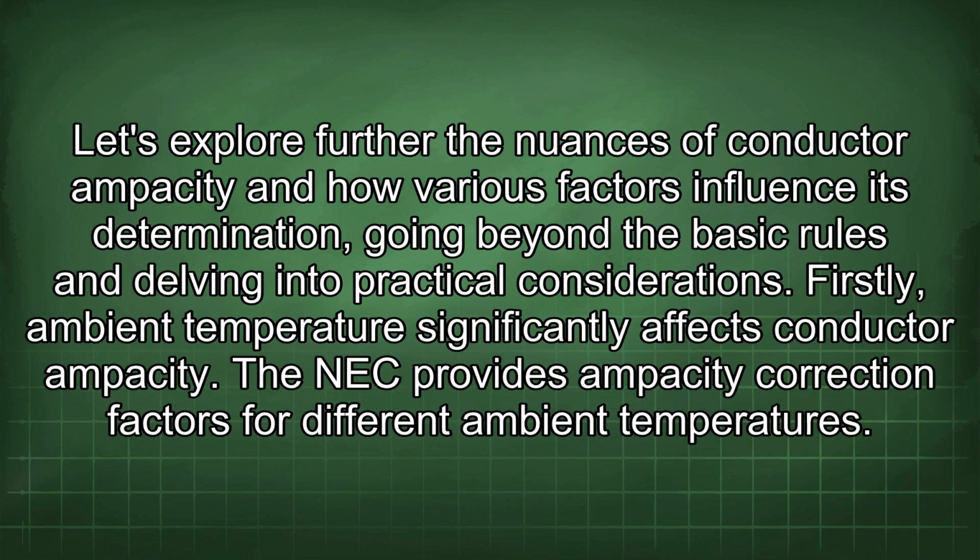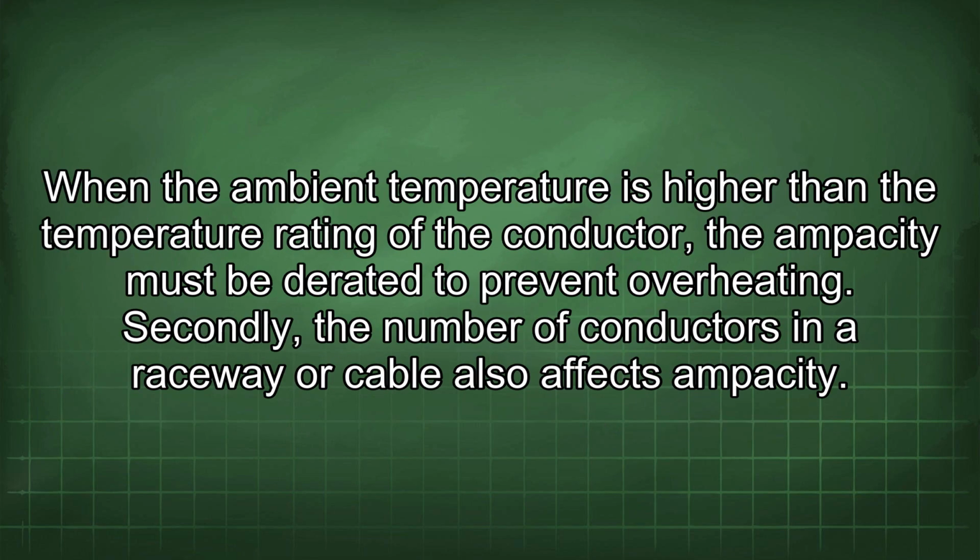Let's explore further the nuances of conductor ampacity and how various factors influence its determination, going beyond the basic rules and delving into practical considerations. Firstly, ambient temperature significantly affects conductor ampacity. The NEC provides ampacity correction factors for different ambient temperatures.